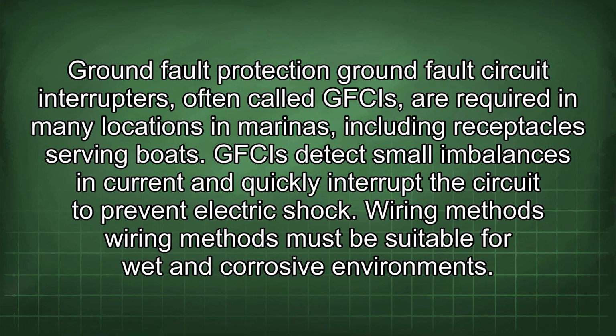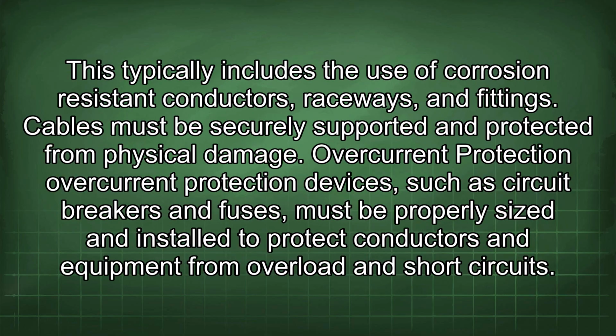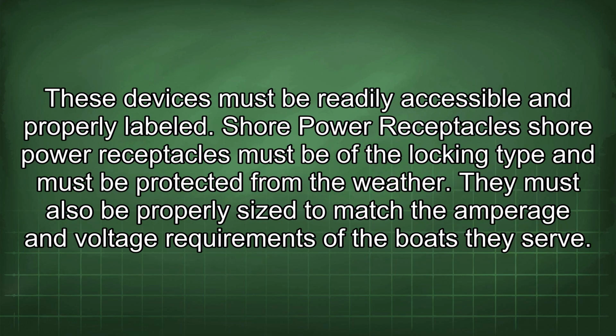Wiring methods. Wiring methods must be suitable for wet and corrosive environments. This typically includes the use of corrosion-resistant conductors, raceways, and fittings. Cables must be securely supported and protected from physical damage. Overcurrent protection. Overcurrent protection devices, such as circuit breakers and fuses, must be properly sized and installed to protect conductors and equipment from overload and short circuits. These devices must be readily accessible and properly labeled.